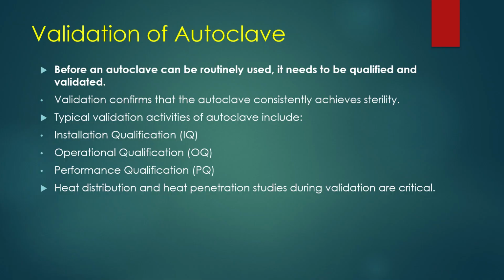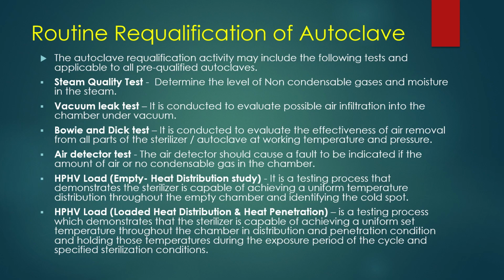Let's see validation of an autoclave. Before an autoclave can be routinely used, it needs to be qualified and validated. Validation confirms that the autoclave consistently achieves sterility. The typical validation activities of an autoclave include installation qualification, operational qualification, and performance qualification. Heat distribution and heat penetration studies during validation are critical. One of the most important aspects of autoclave operation is routine requalification. Let's understand why it is essential. Routine requalification includes a series of tests to verify that pre-qualified autoclave continues to perform effectively, consistently, and in compliance with regulatory requirements. The autoclave requalification activity may include the following tests and applicable to all pre-qualified autoclaves.